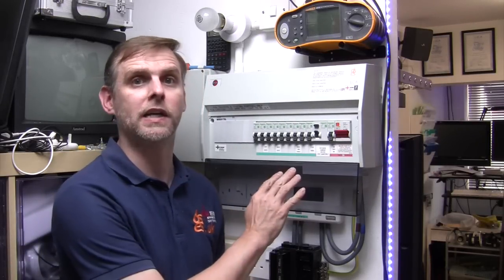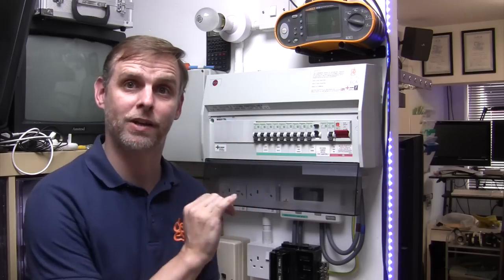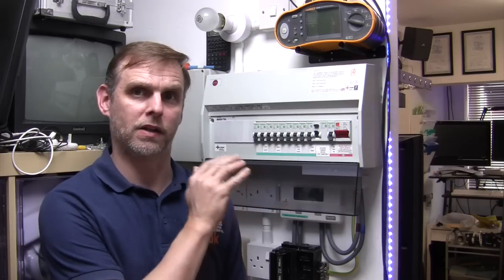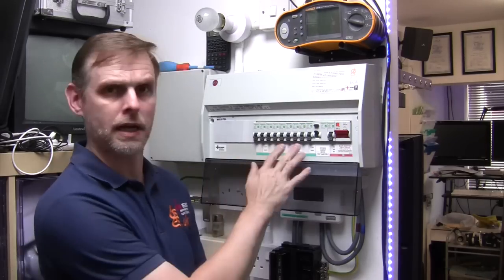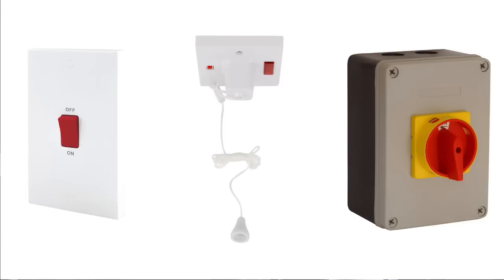While at the point of isolation, there's one other thing we need to do before we can begin work: lock off the circuit so it can't be re-energised while we're on the job. In many cases the point of isolation will be the fuse or circuit breaker position back at the consumer unit or distribution board, as it is here, although there may be a more localised means of isolation, such as a double pole toggle switch, a pull cord isolator, or a rotary isolator.